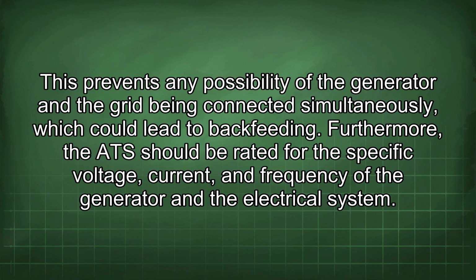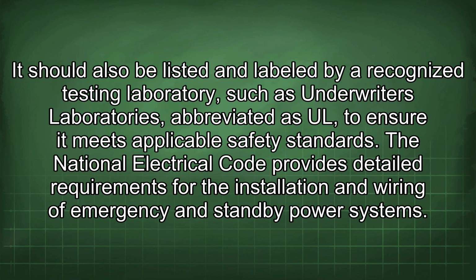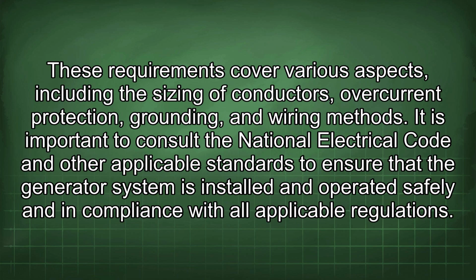Furthermore, the ATS should be rated for the specific voltage, current, and frequency of the generator and the electrical system. It should also be listed and labeled by a recognized testing laboratory, such as Underwriters Laboratories, abbreviated as UL, to ensure it meets applicable safety standards. The National Electrical Code provides detailed requirements for the installation and wiring of emergency and standby power systems. These requirements cover various aspects, including the sizing of conductors, overcurrent protection, grounding, and wiring methods.